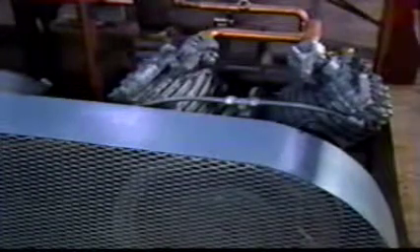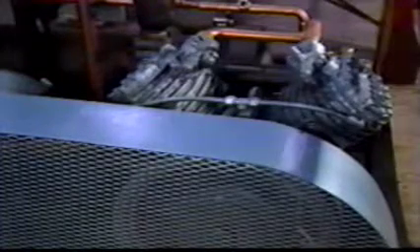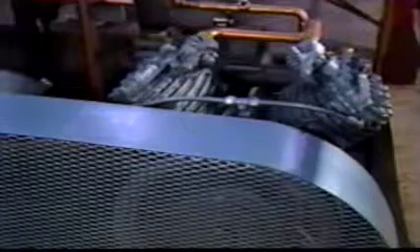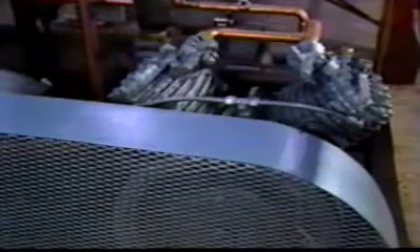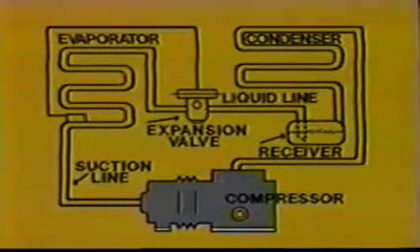The typical air conditioning or refrigeration circuit will circulate hundreds of pounds of refrigerant every hour. The system will work best if this flow is as unrestricted as system design will allow. The very foundation of all refrigerant system performance is pressure difference.